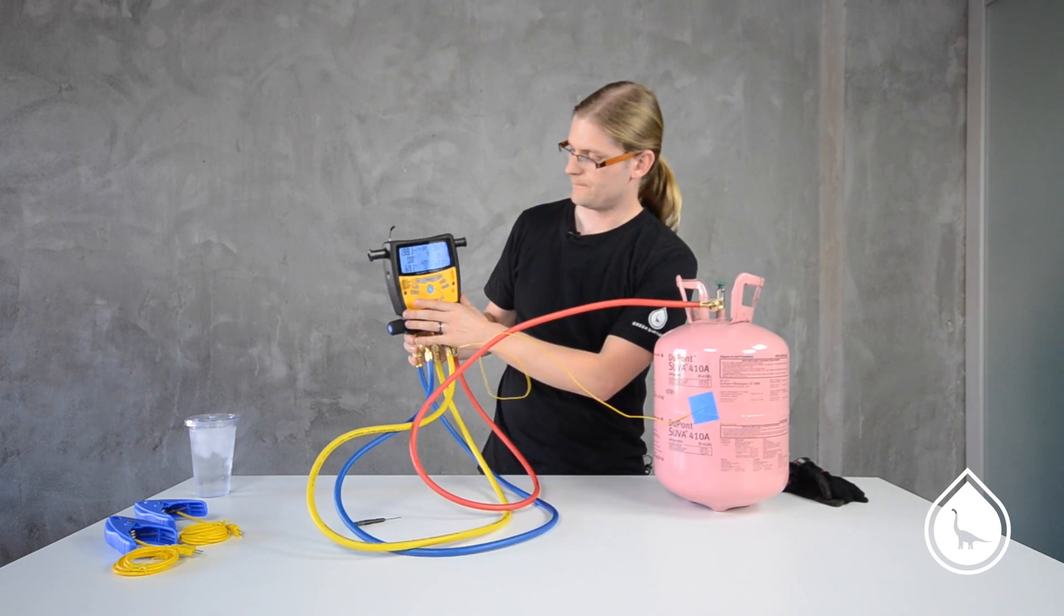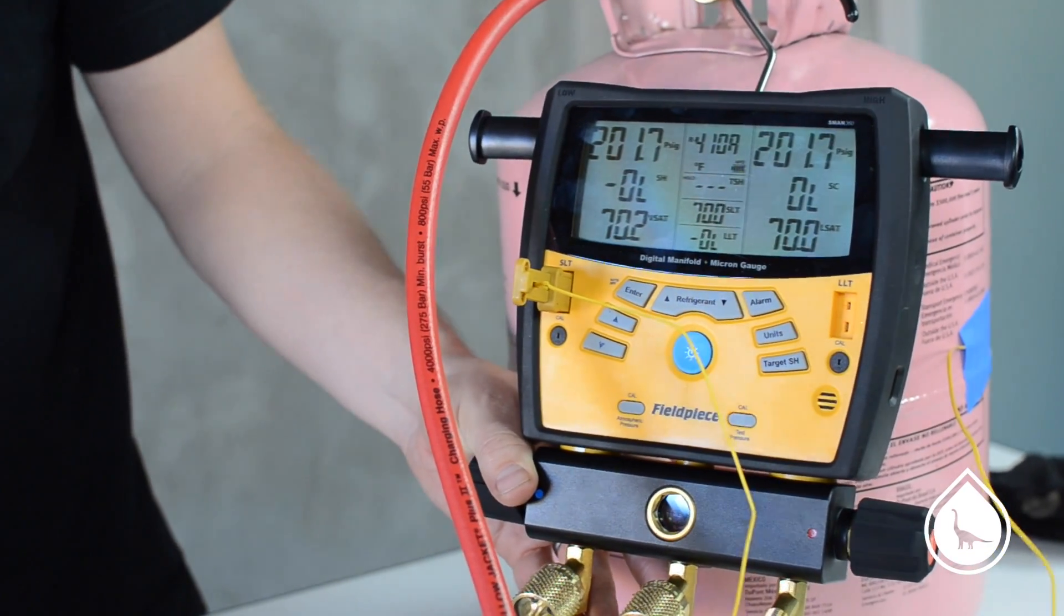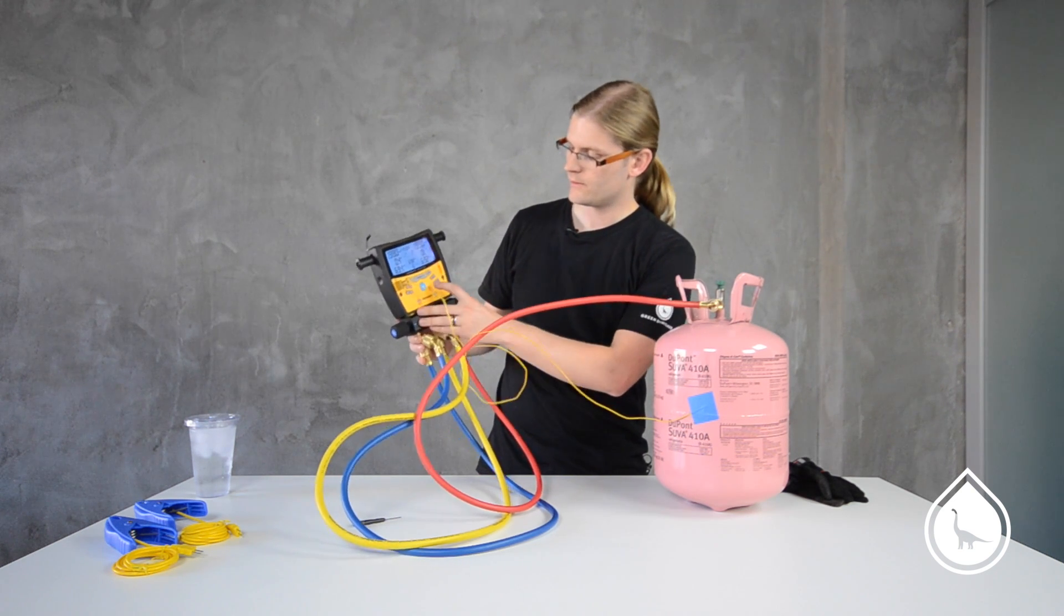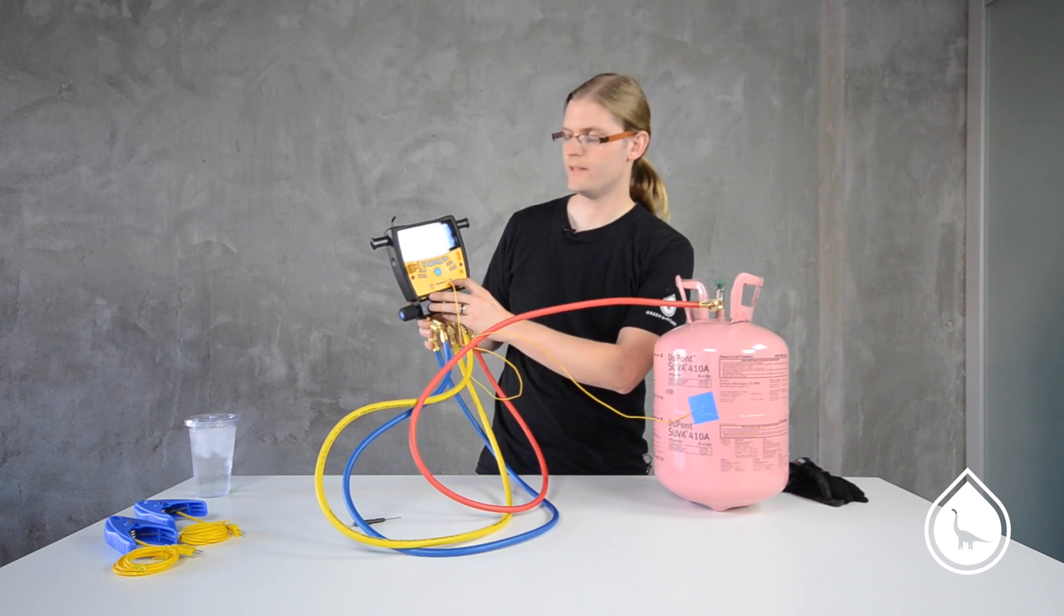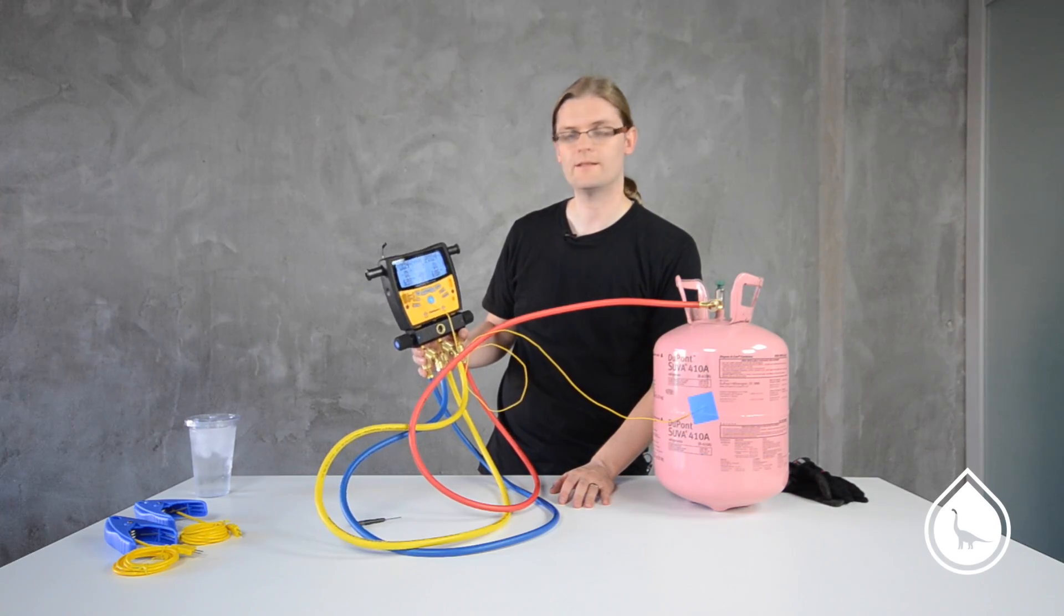All right, so we've got temperatures reading about 70 degrees and pressures reading at about 199. Now we're going to hit the calibrate test pressure button down at the bottom, and it flashes good on both sides, within calibration tolerances, and it's good to use.